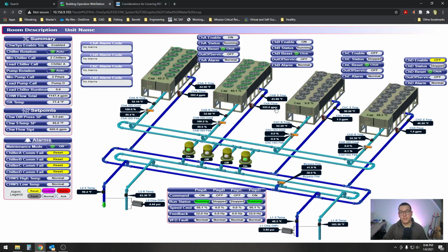So what accomplishes this 550? We know the pumps are pumping water through the system, but it doesn't care about the chiller flow. It only cares about the differential pressure. Well, that's where the bypass valve comes in. So this is literally bypassing water from the supply to the return. As you can see here, it's installed up on the roof, up against the guard railing. If you want to go take a look at it at some point, but that's where that is. So its sole mission in the system is to maintain this 550 set point.